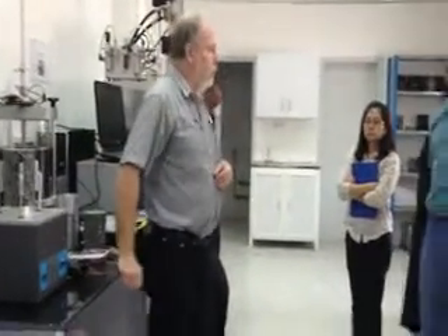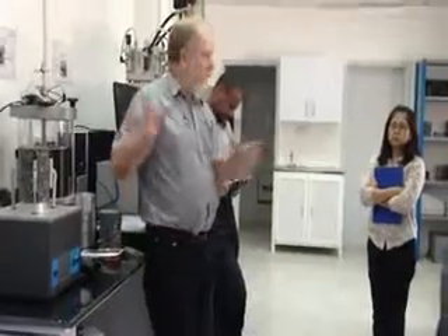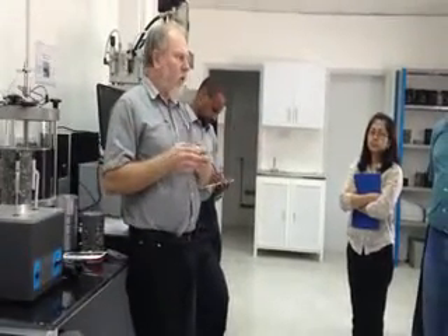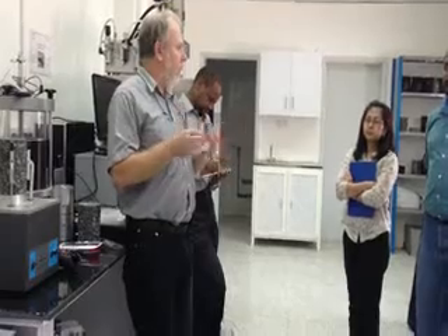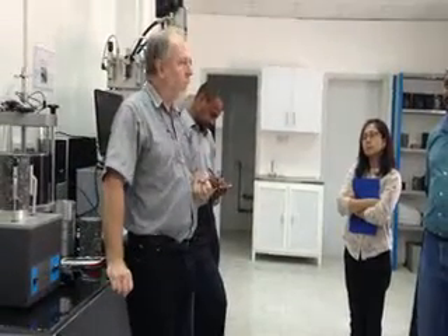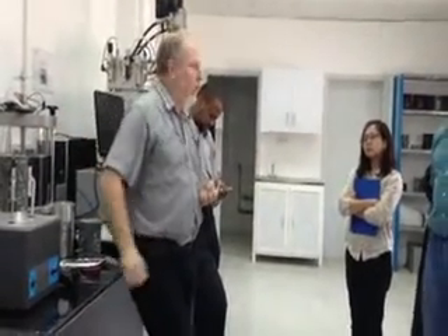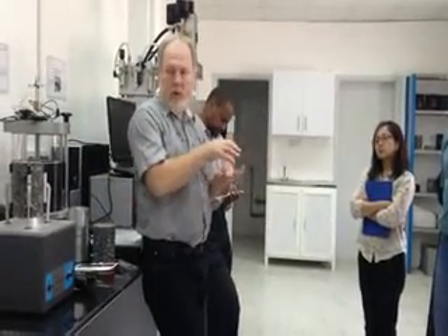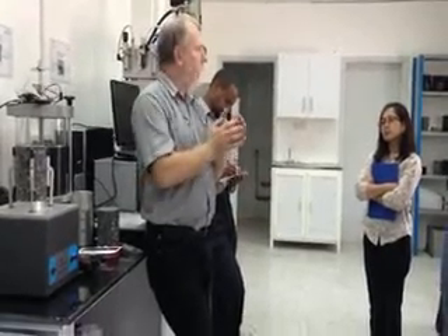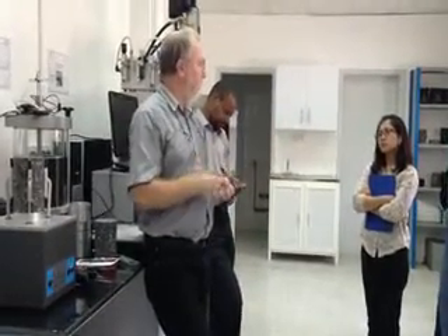And in the test protocol, it originally said that from getting your sample out of conditioning into the machine and ready for a test, you had to do it within 30 seconds. So we had to come up with quite a quick method of getting the sample ready. So we had quite small chambers, so then get the one sample, we can automatically raise it, lower it, and then you can get the temperature back up with minimal disturbance on the sample.